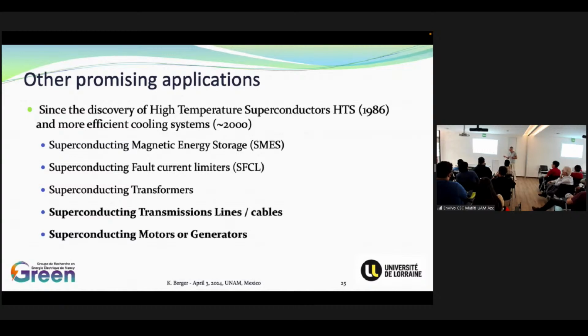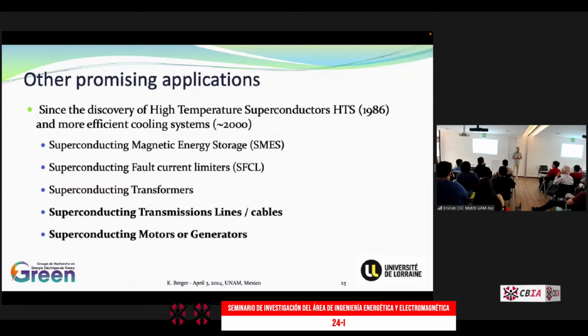Another kind of application is the superconducting fault current limiter. If you use the fact that a superconductor can switch from the superconducting state, which means low resistance, to the normal state, which means high resistance, you can build a system that, in case of high currents such as a short circuit, reduces the amplitude of these currents by introducing high impedance or high resistance, decreasing the peak current. This is what we call a fault current limiter using superconductors.